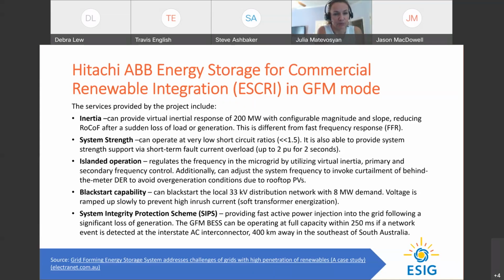It's also able to provide system strength support with short overcurrent capability of up to 2 per units for 2 seconds. It can, as I mentioned, do island operation utilizing virtual inertia, and has also primary and secondary frequency control over there. Additionally, it can adjust frequency of the island to go up when there is over generation conditions in an island, because you can imagine they have 8 megawatt peak load connected together with 91 megawatt wind farm, and then 2 megawatt of rooftop solar, as I mentioned. So what it can do, it increases frequency of the island, and that makes distributed rooftop solar trip offline, so that way it can control the power production. It has black start capability, so it can start that islanded grid and then re-energize with the rest of the grid, also using this soft start method that I talked about before.